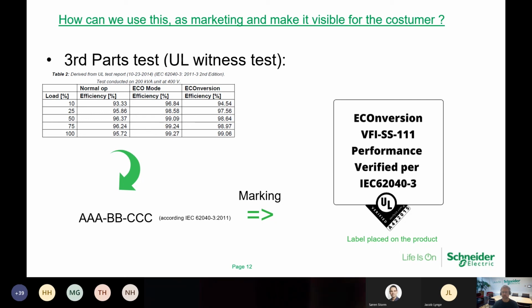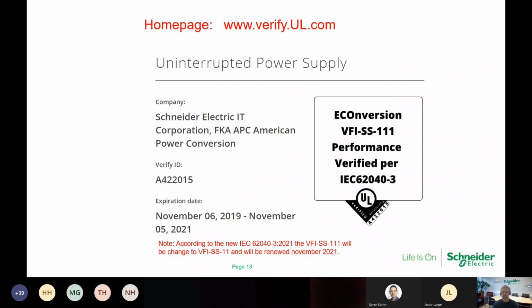The label shown on the right side was designed to be placed on the UPS. If we take a look at the label, we can see the home page at the bottom of the label, verify.ul.com, and by typing in the number also on the label, A422015, we get the certificate of the classification. This label has been placed on the product and used to show that this product is verified by a third party to be a class 1 UPS at the performance output classification according to the IEC standard 62040-3.